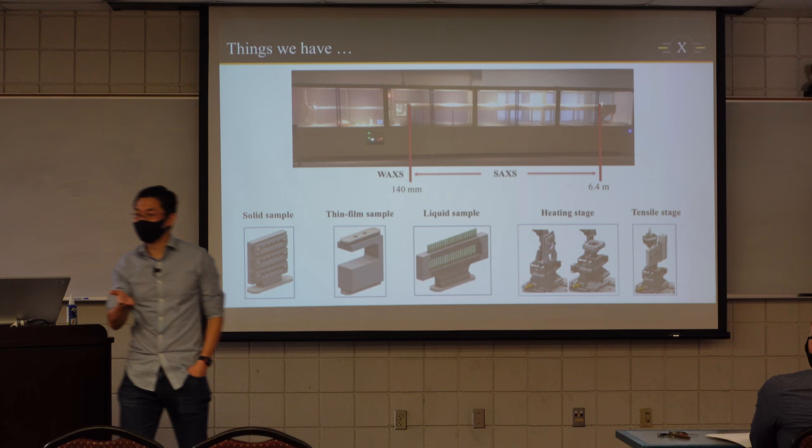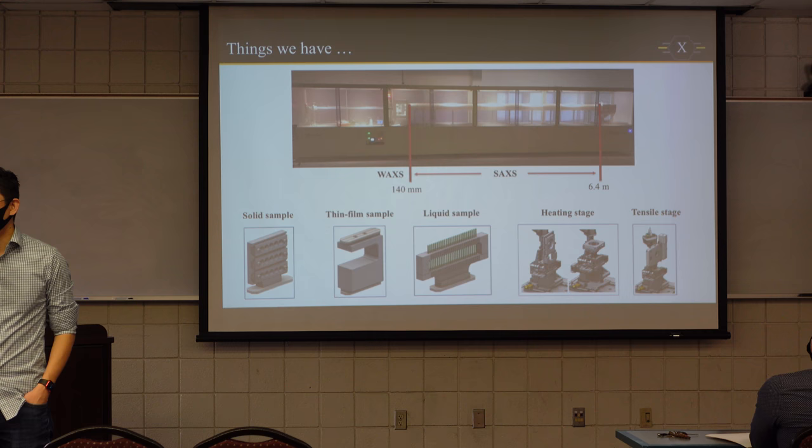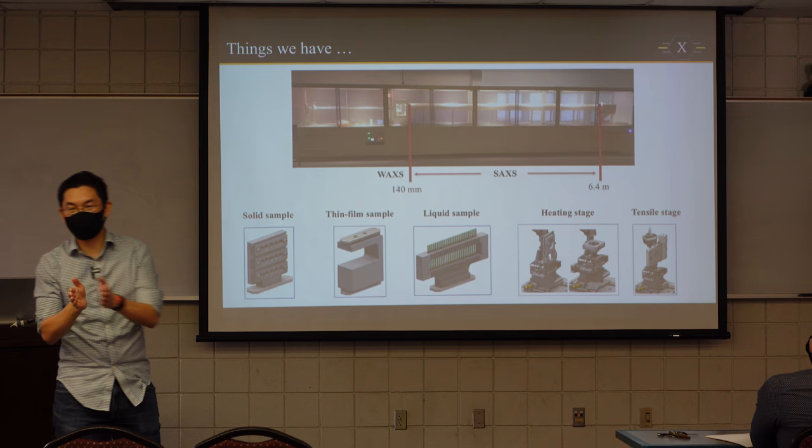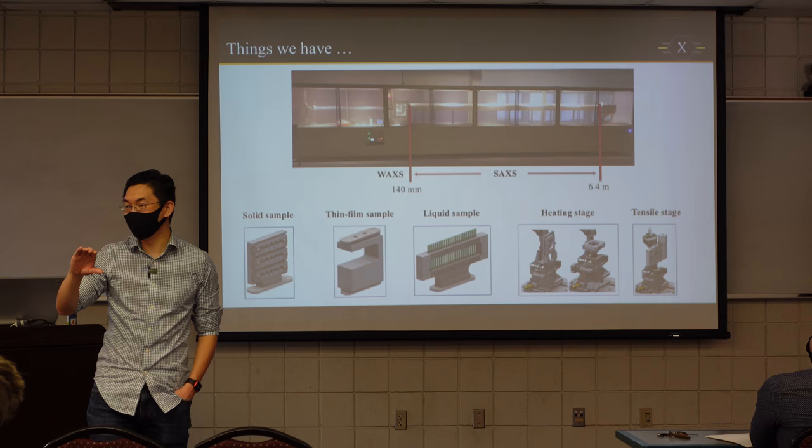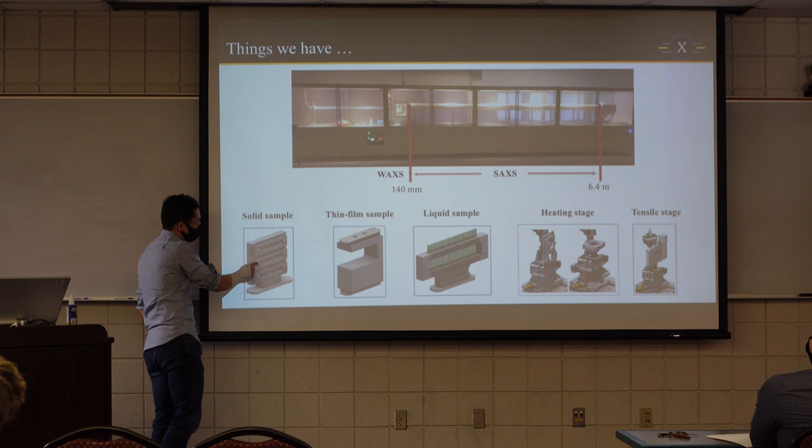So Isaiah, yes. Does the X-ray enter through the more narrow opening and then come into the scattering? Yeah, that's exactly right. It's to accommodate wide angle scattering angle. If you have a very narrow exit angle, the beam is going to be blocked by your sample holder. So this is particularly useful for wide angle scattering.